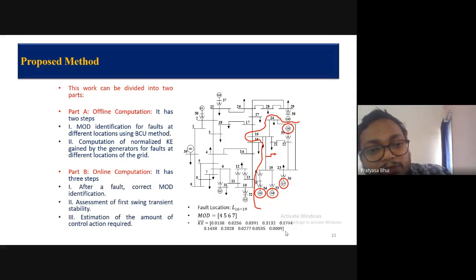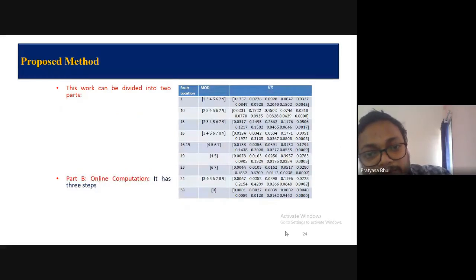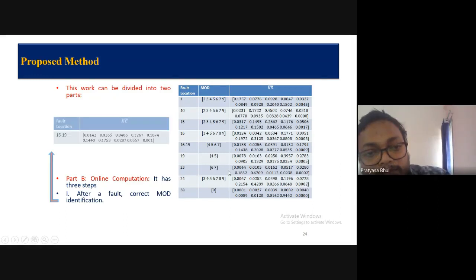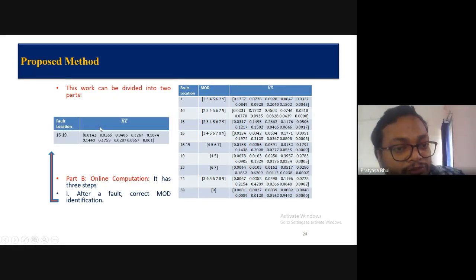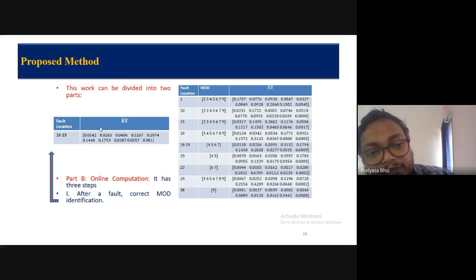Now in the online part, when there is a fault, you build a lookup table like this: fault location, mode of the disturbance, and the kinetic energy. So whenever there is a fault, you measure the generator speeds, calculate the kinetic energy, and then normalize with the total energy. So you get this array, and then you compare with the lookup table.